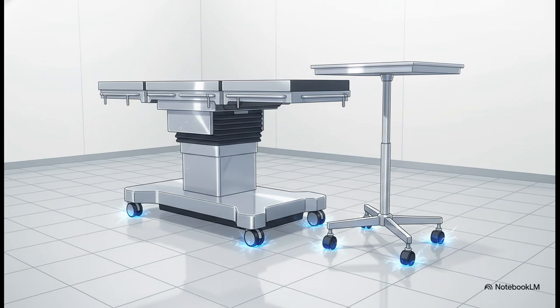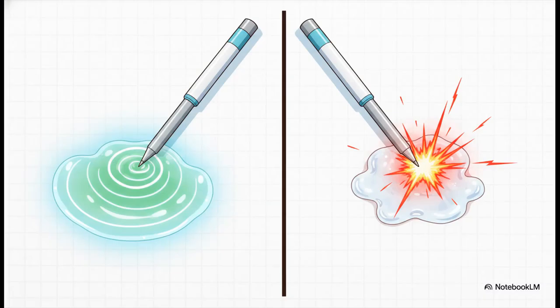And remember that explosive static electricity we talked about earlier? To prevent it, virtually every piece of furniture from the tables to the adjustable Mayo stands overhanging the patient rolls on specialized casters. These wheels are made of conductive metal or rubber to quietly ground electrical charges into that engineered conductive floor. Speaking of electricity, our source gives a very intense, specific medical warning about electrosurgical tools.